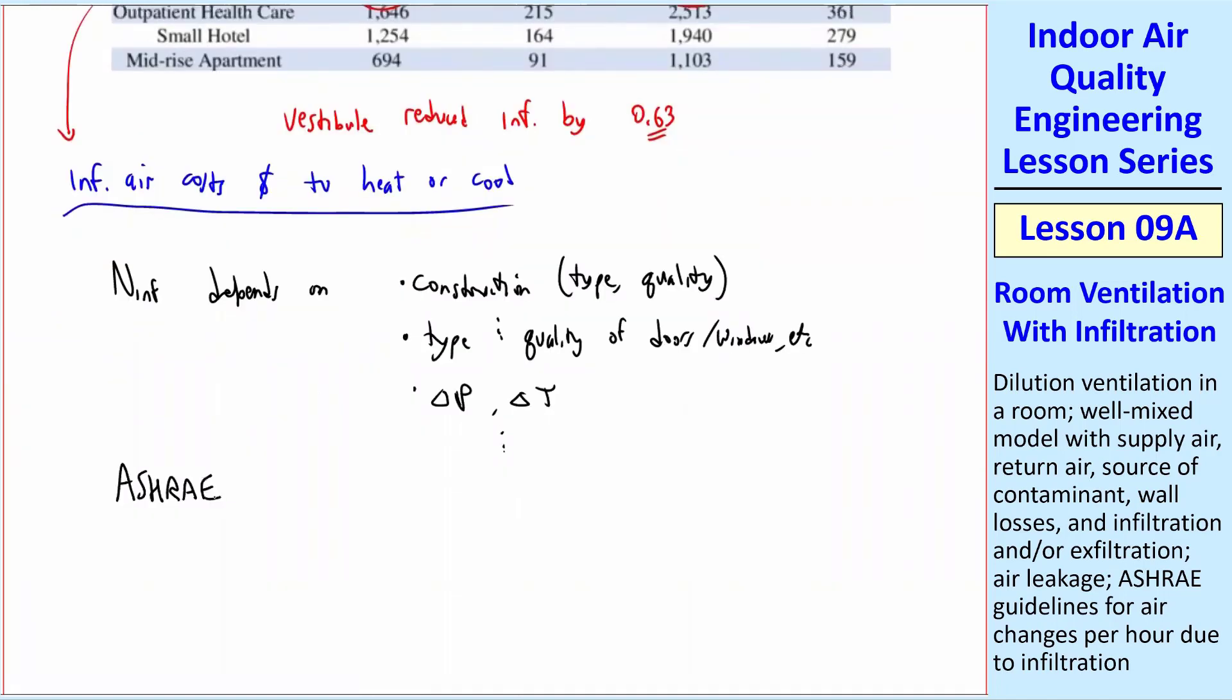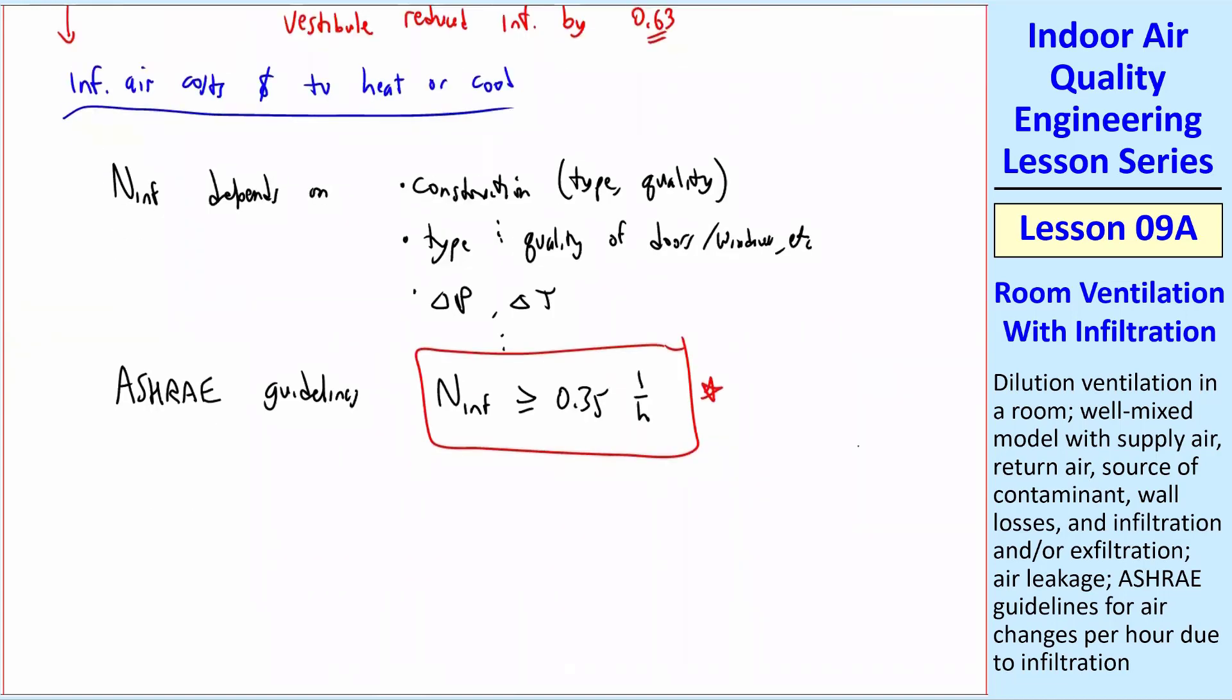ASHRAE, American Society of Heating, Refrigeration, and Air Conditioning Engineers, they have guidelines for buildings, and that is that N infiltration must be greater than or equal to 0.35 per hour. You need to have about a third of the room change per hour. Otherwise, if it's not that, you would have unhealthy air. There's too many people breathing. What ASHRAE says is that if the natural infiltration is less than 0.35 per hour, then you require forced ventilation.